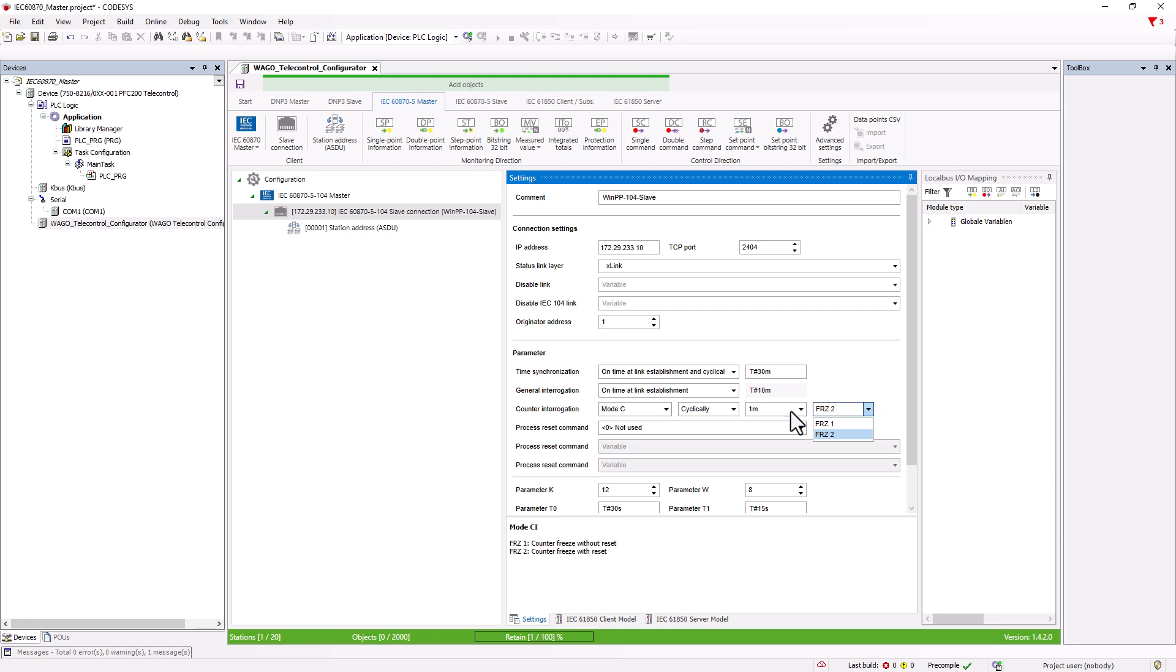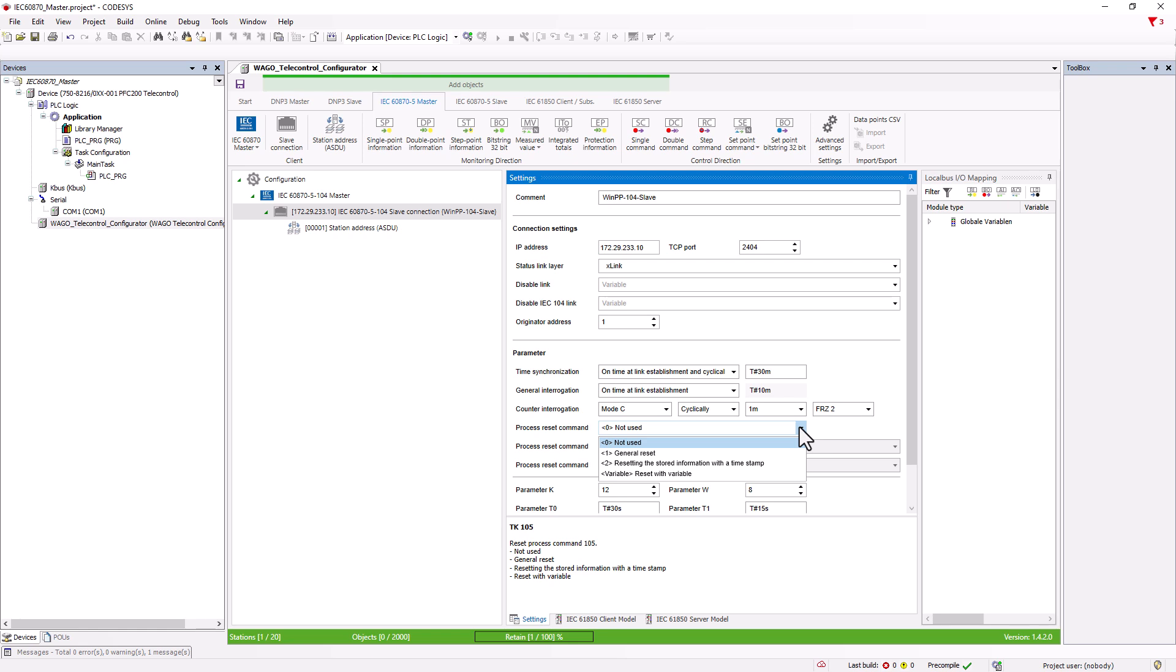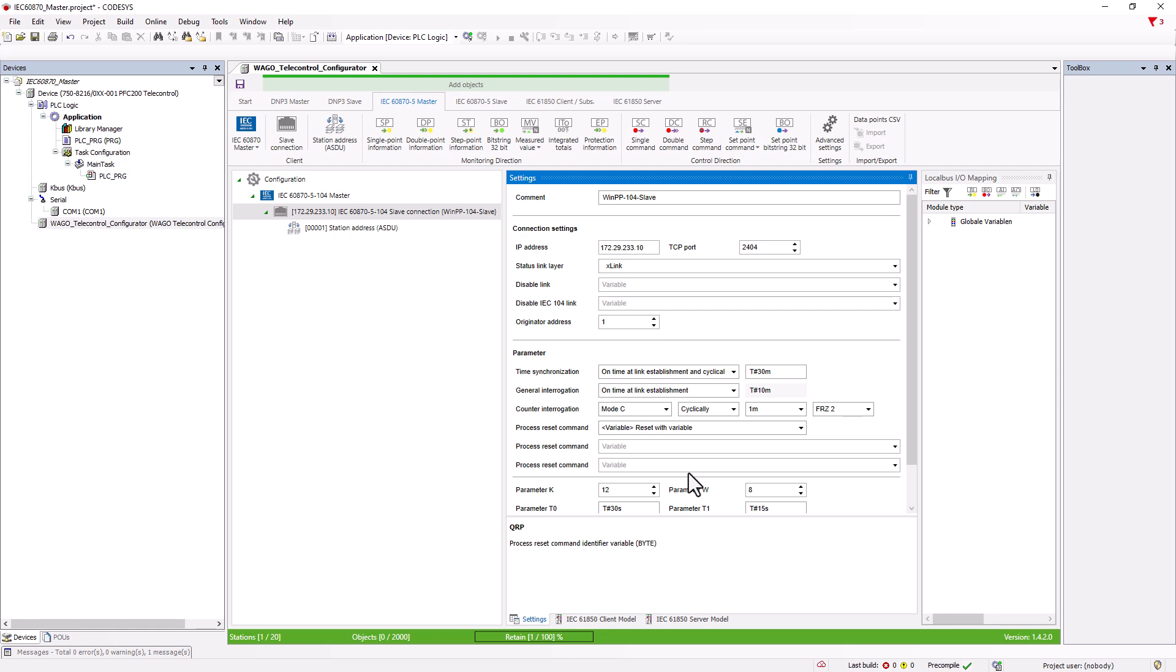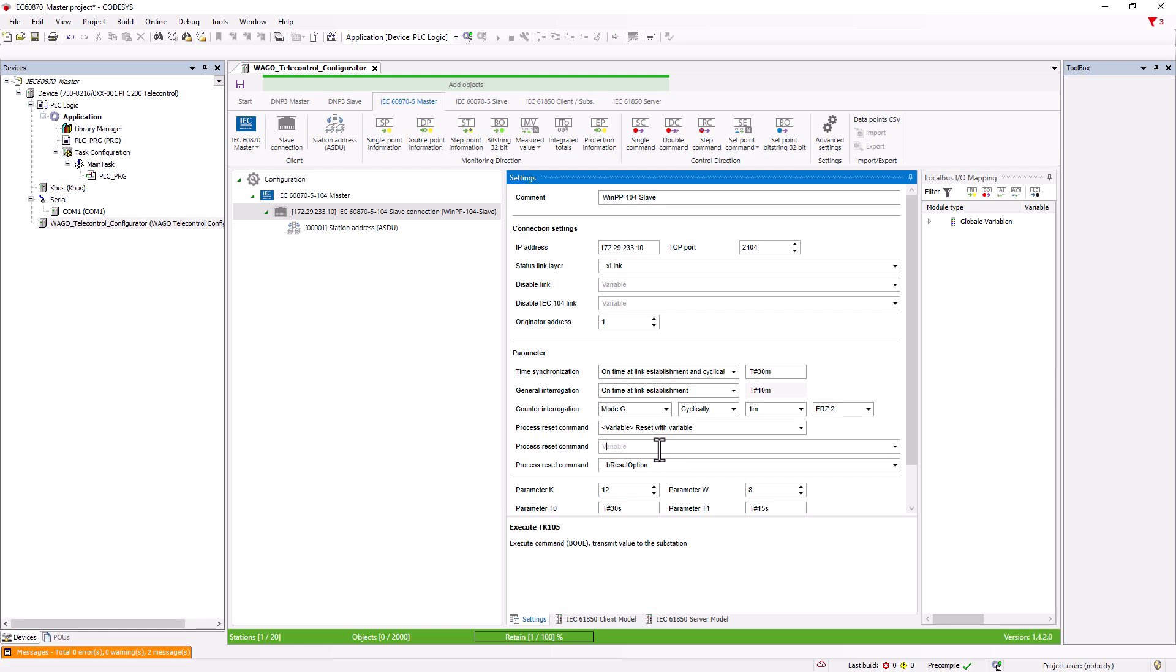Here, we can set which reset is expected from the slave when the reset telegram QRP is sent. Zero for not used, that means no reset is possible. One for a general reset or Two, resetting of all stored values with a timestamp. And the option variable, reset with variable, which we assign in this field as a byte variable and which then contains one of the three reset options, zero, one or two. In this line, we can specify a bool variable to trigger the reset.